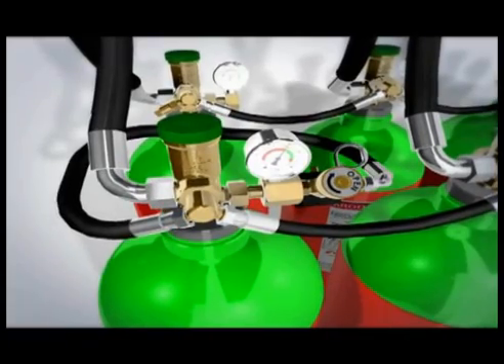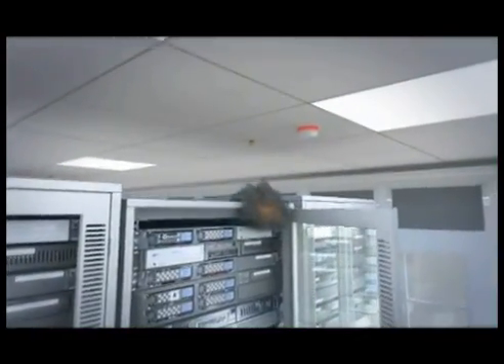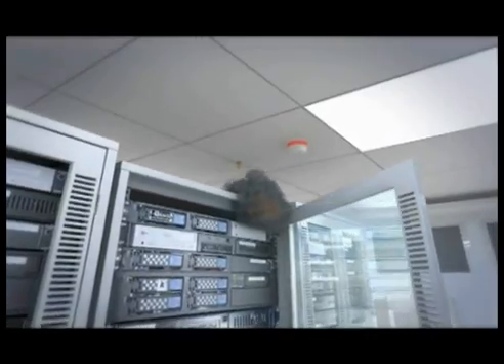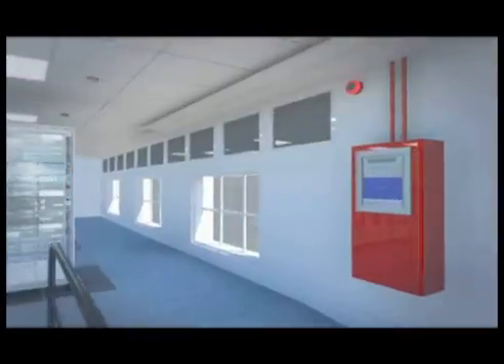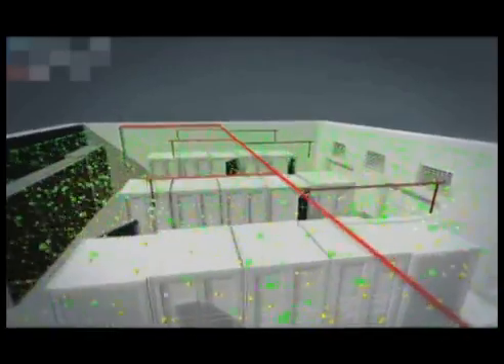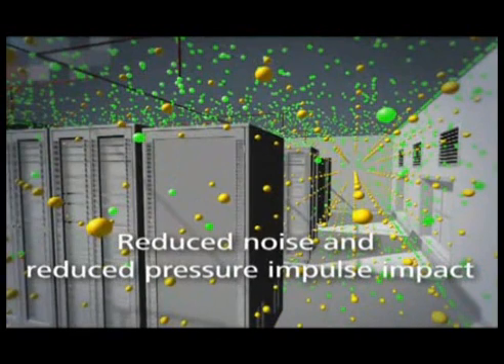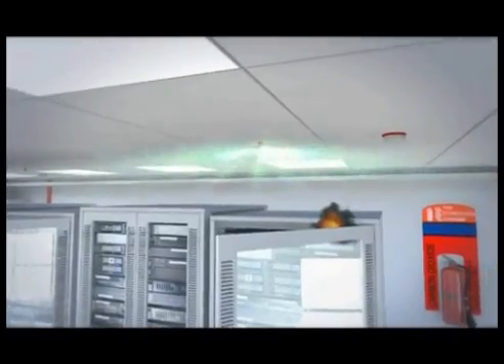In the event of a real fire, the detection and alarm system will be configured to deliver an accurate and timely indication of a fire condition. Following the initial alarm and a preset delay, a final alarm is given and the control panel energises the solenoid on the Argonite C60 release unit. This controlled flow discharge has both reduced noise and reduced pressure impulse impact, which could otherwise affect sensitive electromechanical equipment. The fire is suppressed rapidly, limiting the fire damage.